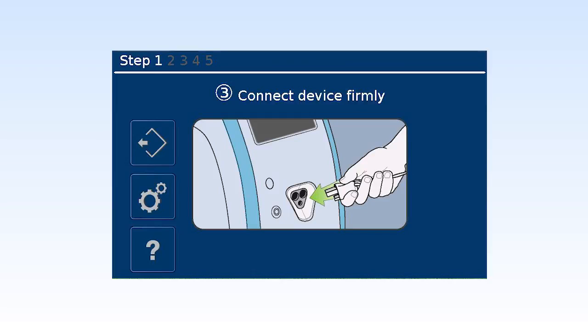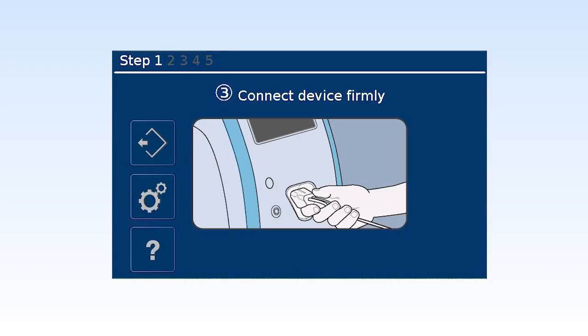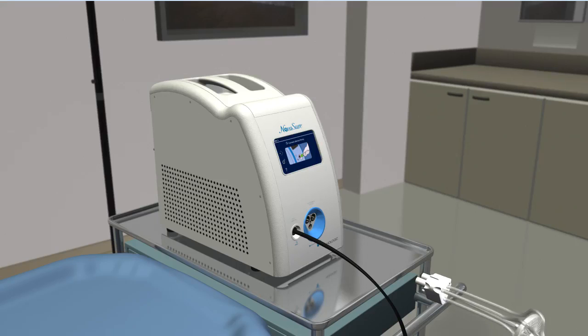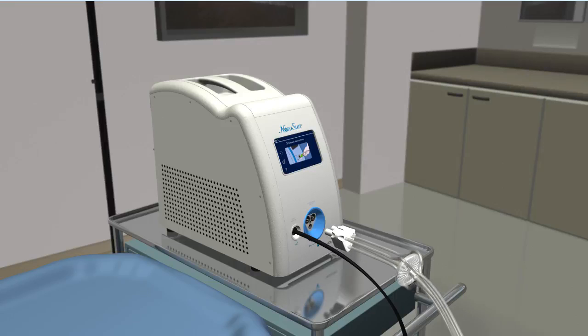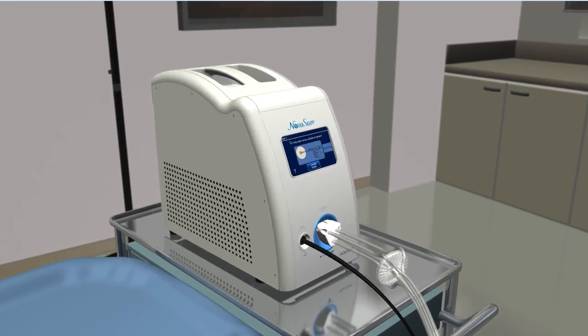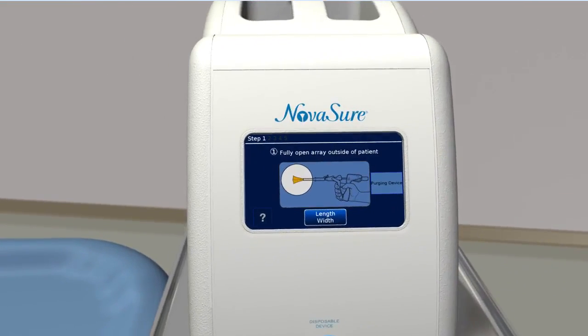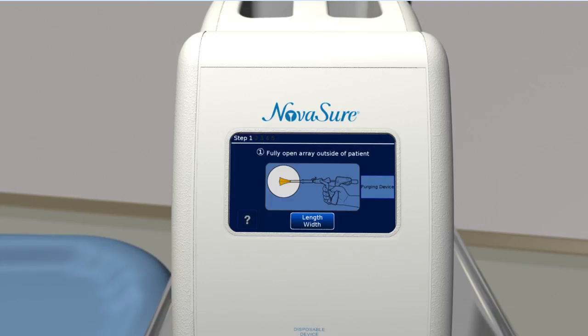Before inserting the NovaSure device into the patient, connect the disposable device cord to the appropriate port on the front panel of the controller. As soon as you plug in the device, you will hear an audible beep. This beep indicates that CO2 is flowing and that the disposable device and tubing is being purged. The purge operation takes approximately 10 seconds and must be performed before the device is inserted into the patient.